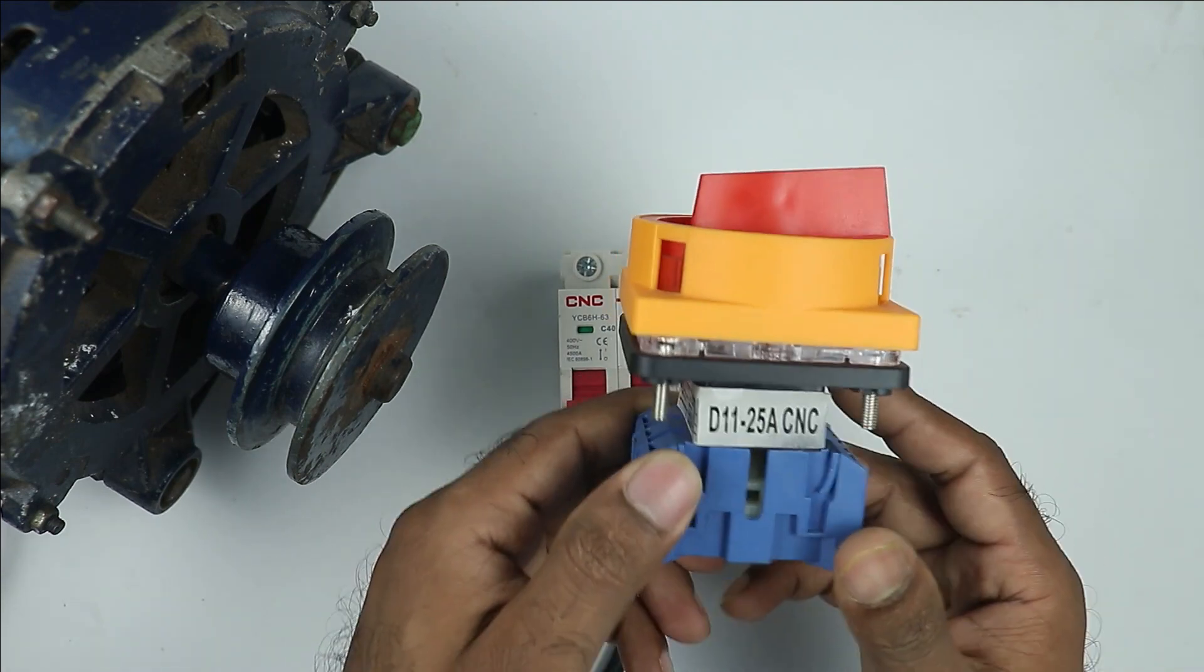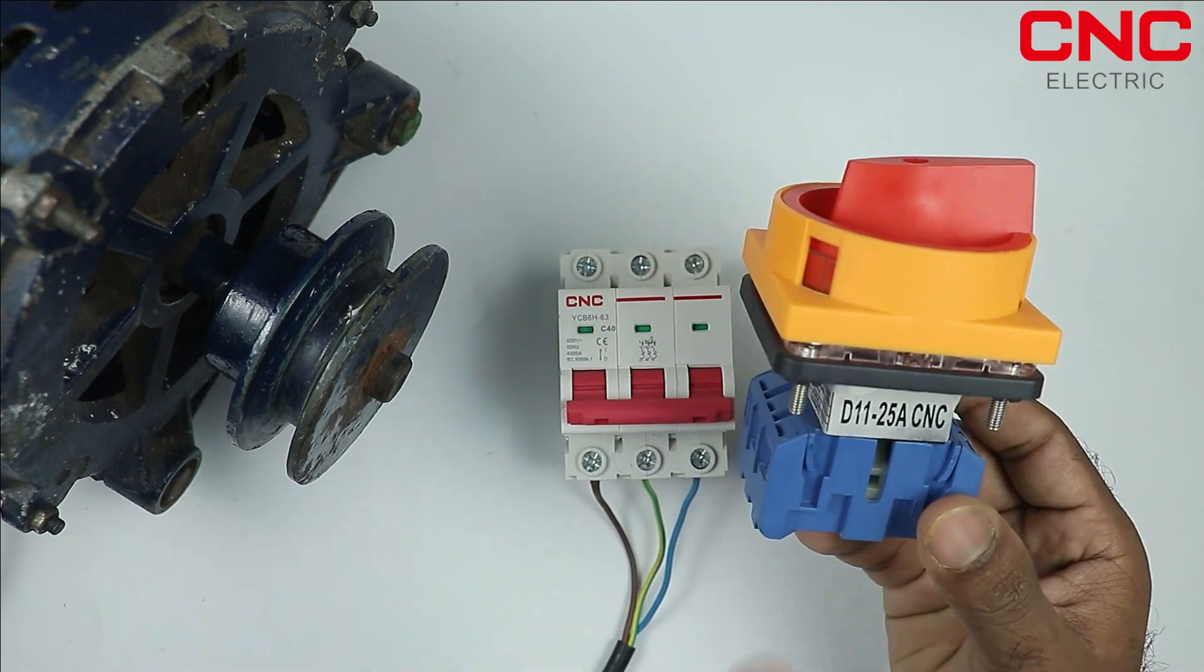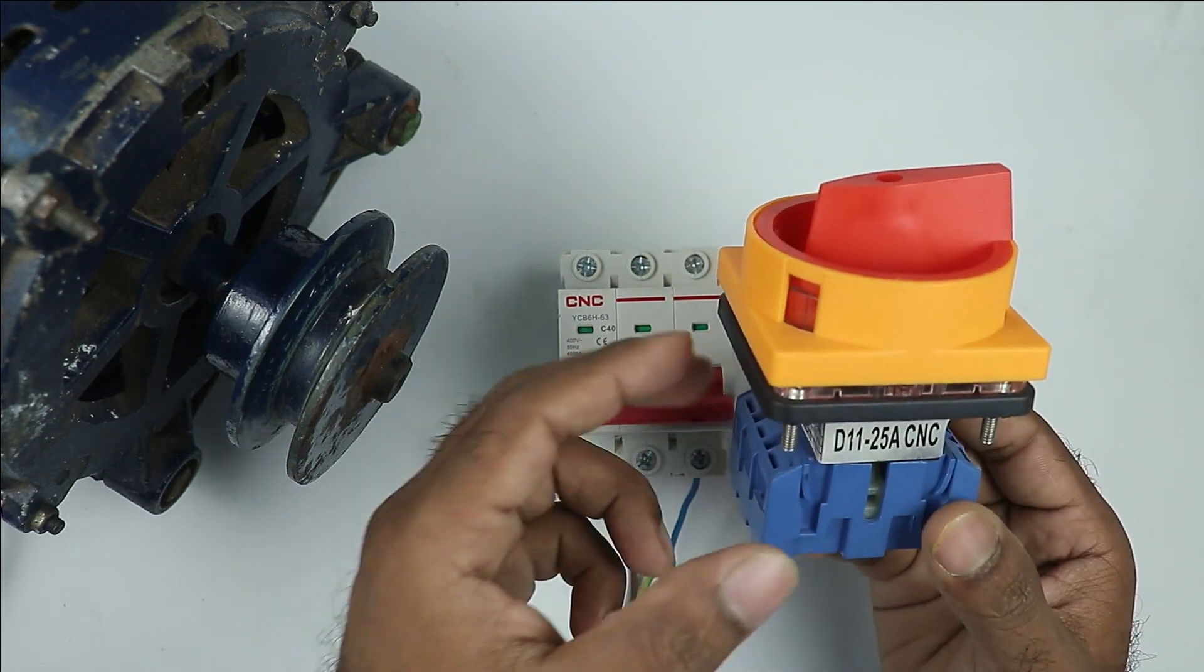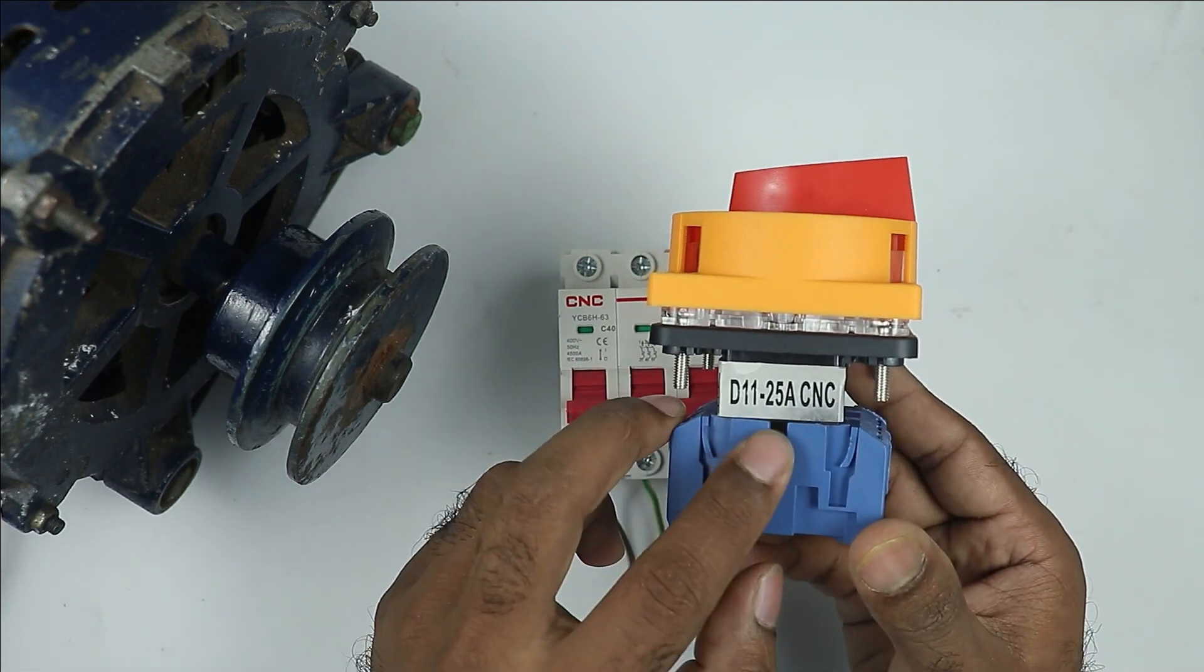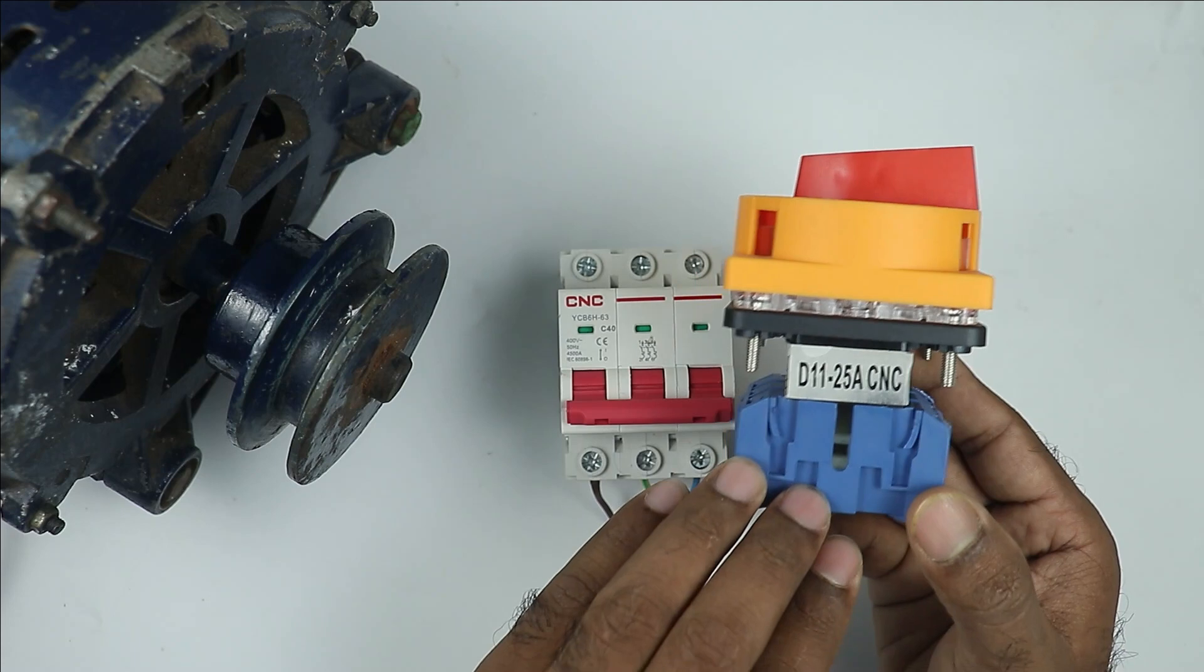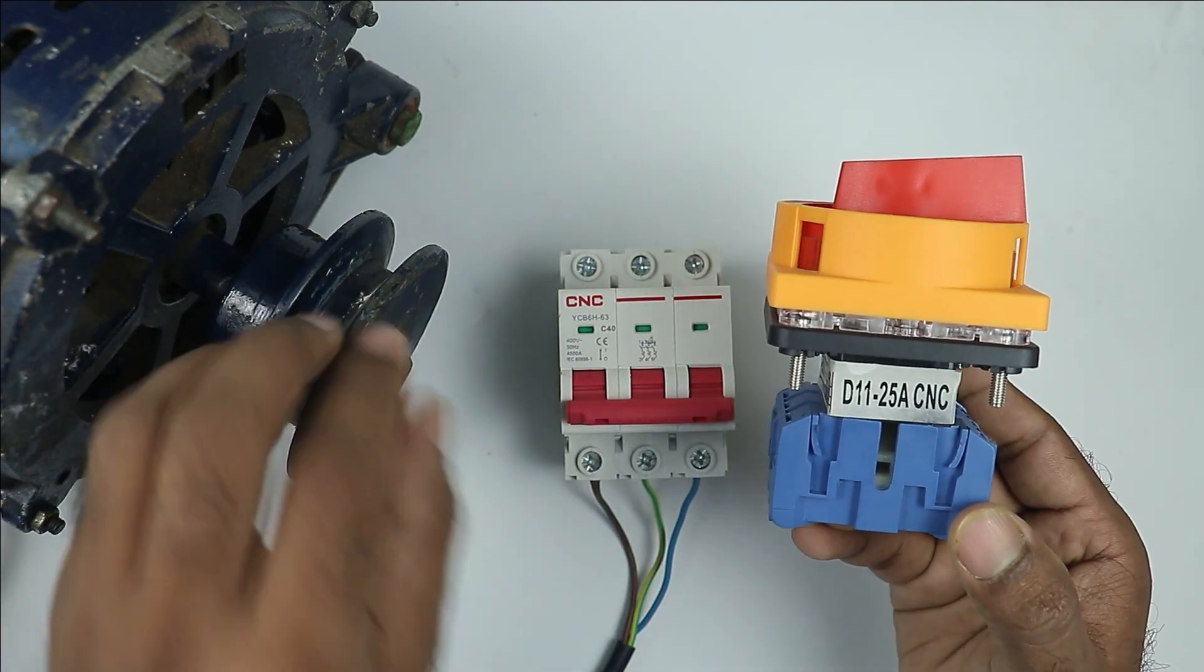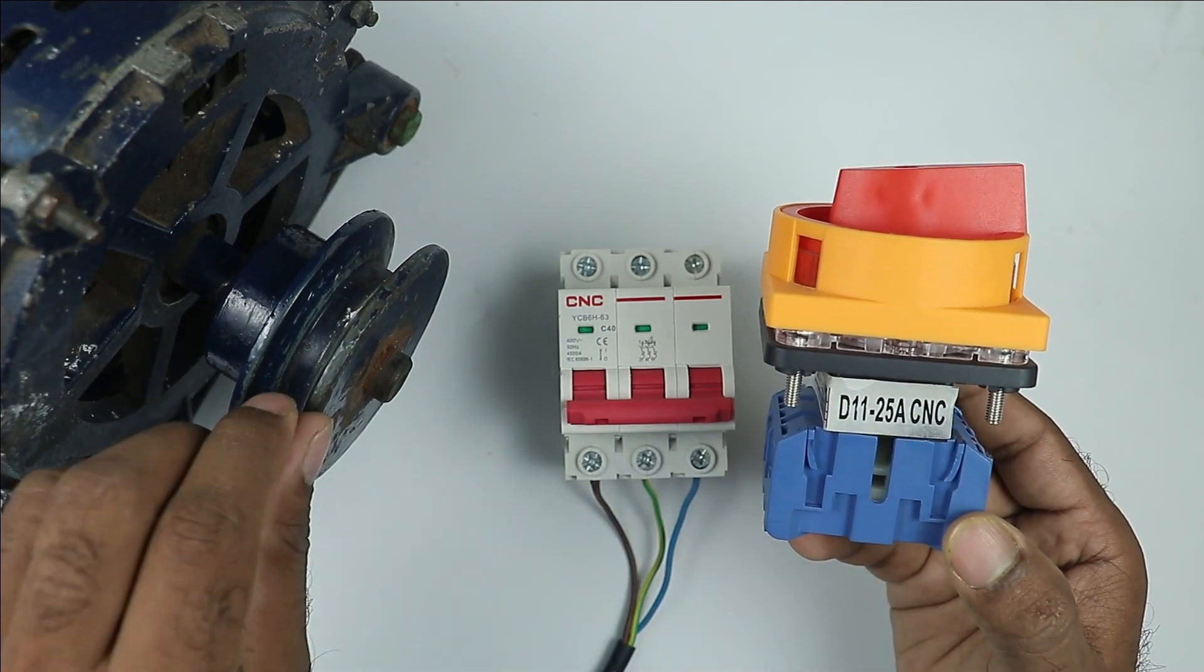This rotary switch I have now is manufactured by CNC company. You can see the model number here. Now, before using this rotary switch, you have to first check how much maximum current can flow through this switch. You can see here 25A is written. This means if the motor's maximum current rating is 25A, then you can use this switch.